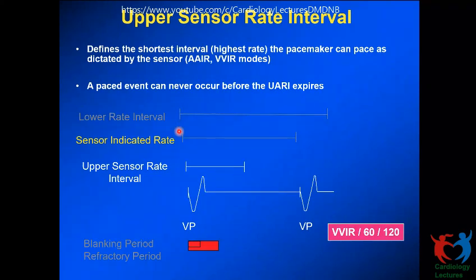The easy way to deal with the upper sensor rate is to consider the sensor indicated rate to be the lower rate provided by the pacemaker at this instant for that patient. Let us say my lower rate is 60, upper sensor rate is 120 beats per minute. Now this patient is doing a gentle walk, and the sensor says pace at 80 beats per minute. So 80 beats per minute at this instant can be thought of as the lower rate provided by the pacemaker, so that your timing cycle will fall into place. The patient goes to sleep, then the sensor is not vibrating, and it will pace at the lower rate. So this is the lower rate at this point.